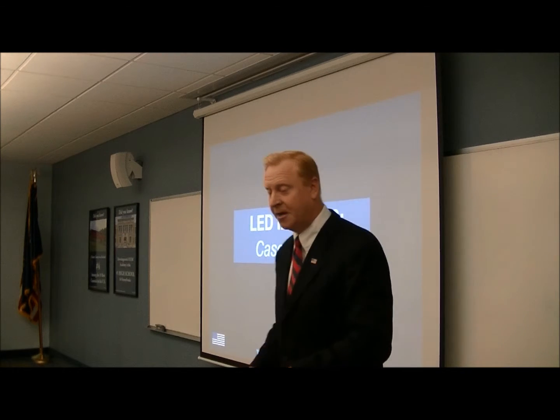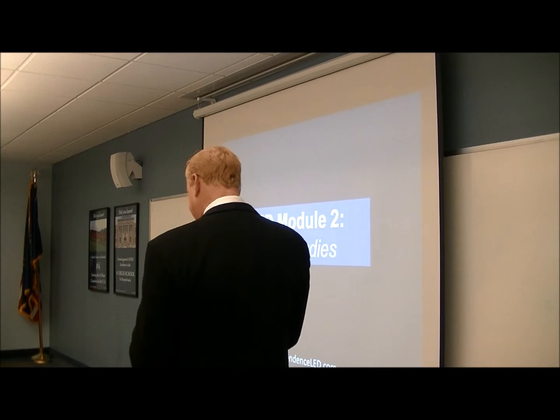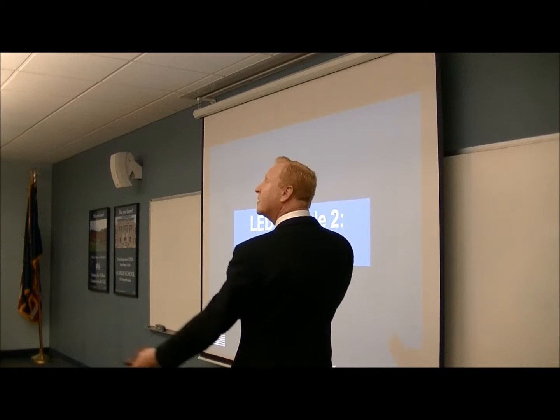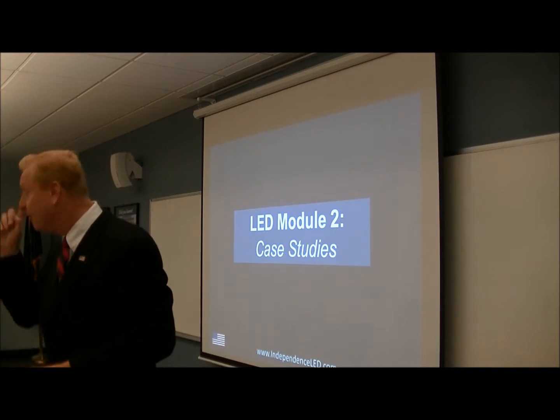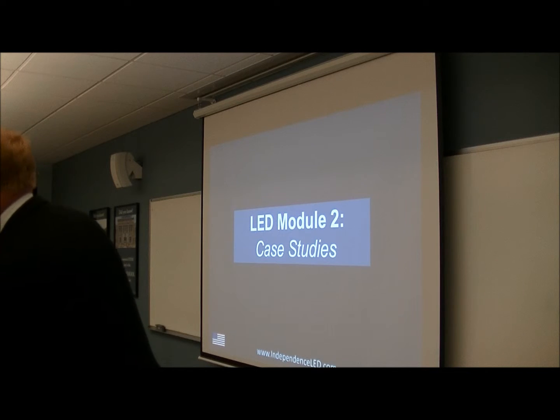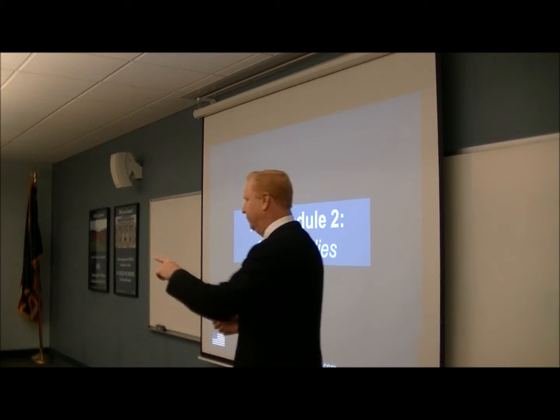We're going to bring out our foot candle meter and we're going to run the light output and we're going to see if it matches what you told me was going to come out of the ceiling. And we're going to make an informed decision, not from looking at the price of a lighting technology.